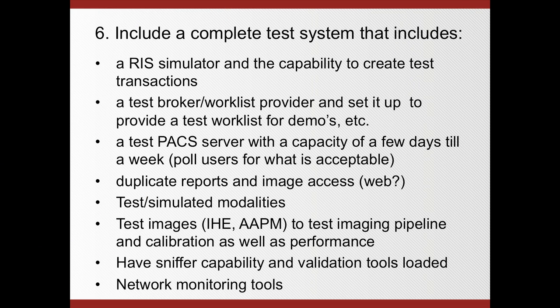An important part is the test system. A test system will be a RIS simulator and a capability to create test transactions. The good news is that HL7 as a standard allows you to create messages that are identified as test messages, so people know to ignore them. So if you get a test order, people know, okay, I'm not going to look for Jane Smith in the waiting room to do an x-ray, because they know it's a test message.